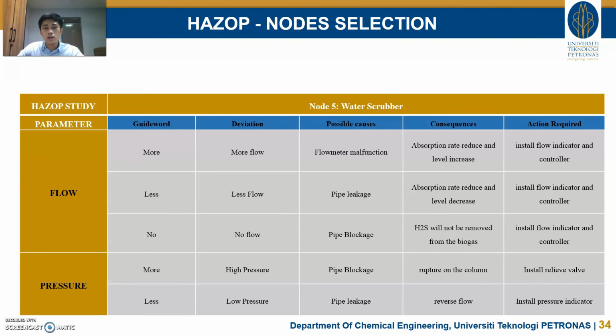For no flow, the cause is pipe blockage. Consequence, H2S will not be removed from the biogas, and action required is to install flow indicator and controller. For pressure, high pressure caused by pipe blockage will lead to rupture on the column, and action required is to install relief valve. For low pressure, cause pipe leakage. Consequence, reverse flow, and action required is to install pressure indicator.